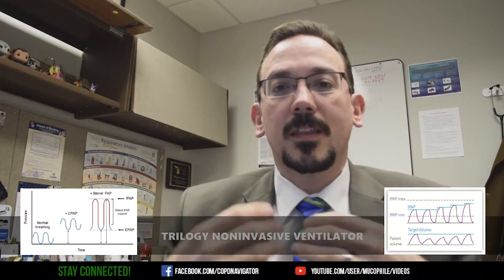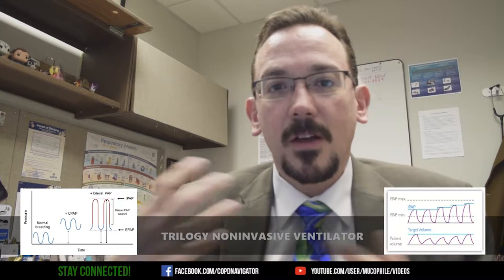The Trilogy has a mode called AVAPS, which basically modifies the pressure setting to target a particular tidal volume. When we have pressure ventilation, it's very sensitive to the condition of your lungs. If your resistance changes or anything like that, the delivered volume will change too.